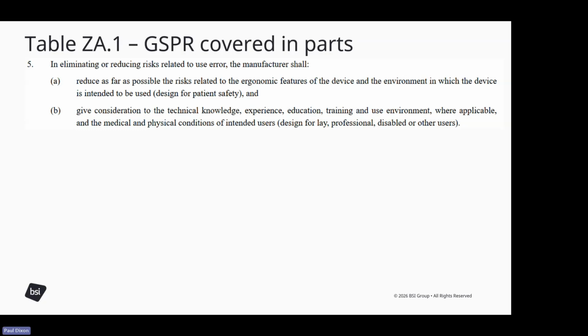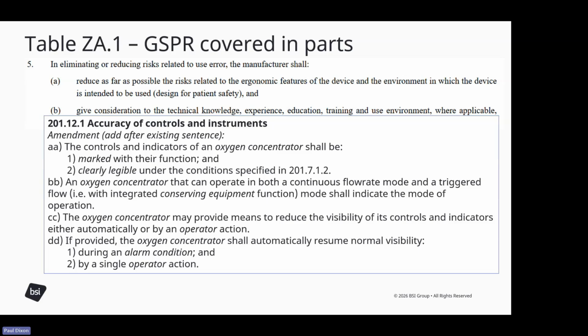Another example, this one is the only example I have of a clause within the general section, so GSPR within the general section. Manufacturers shall reduce as far as possible risks related to ergonomic features of the device and the environment, and give consideration to the technical knowledge, experience, etc. of users. In the case of this standard, it is ISO 80601-2-69, which is a standard for oxygen concentrators used in the home. Again, it's a 60601 style standard.